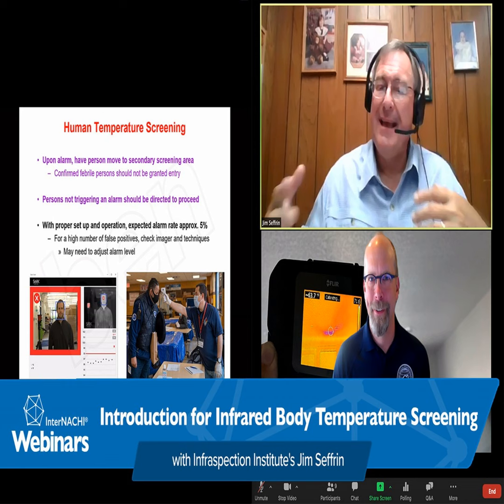When it comes to ensuring imager performance, imager readings should be cross-verified with a clinical grade thermometer prior to commencing the screening of entrants or at regular intervals thereafter. If disagreement is found, you need to find out the cause for this and discontinue your screening until any problems that you found are corrected.